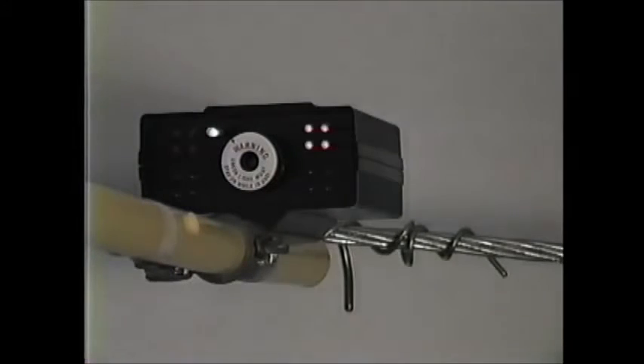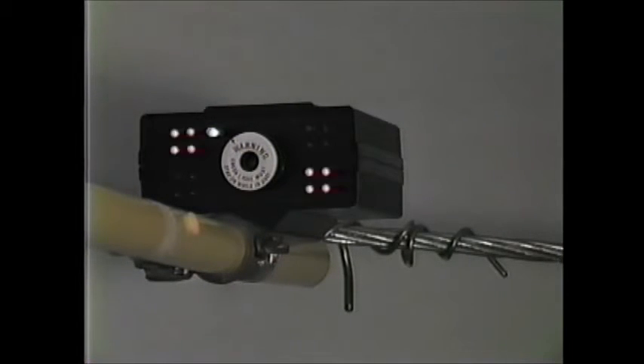We will now raise the voltage up between 7,000 and 11,000 volts, which will pick up the third bank of lights. This would be the normal operating voltage for a 12,470 volt system, 13.8, or a 14.4 kV system.